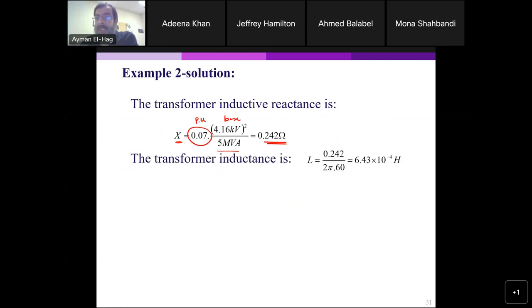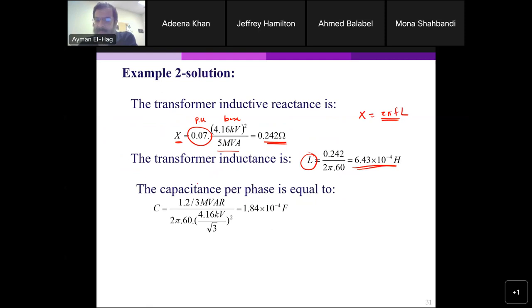Now, from the reactance, you can get the L, how much L in your system. So the L is coming only from the transformer. We know that X is equal to 2 pi f times L. So divide by 2 pi f, which is here 60 hertz, and you will get how much L you have in your system. Now, for the capacitor, we have seen this. This is your omega. This is your voltage, basically the single line to ground, so you divide by root 3. And you take the single phase, which is 1.2 MVAR divided by 3. If you have the three phase, it will be exactly the same formula. So that is your C.